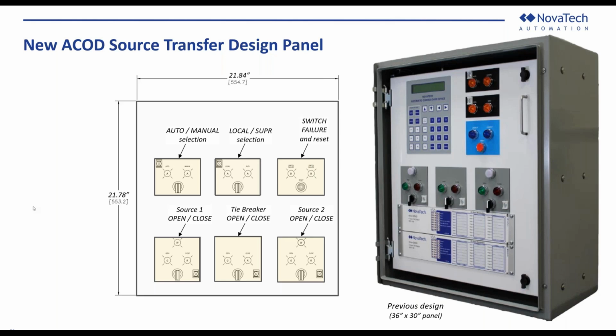This all fit on a panel that is in a custom 36 by 30 inch enclosure. As was shown on the previous slide, this uses different components for each of those functions. The Bitronics PowerPlex 2 meter is there for the PT connections, and then DDIOs provide all the I/O, and an Orion LXM as the head unit.